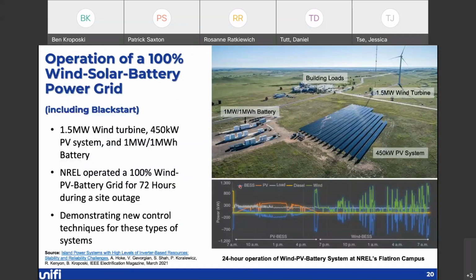I'll just point out that, again, these systems are not impossible to build. This is an example. We actually had our substation at one of our campus facilities go out on us, where we lost the utility for several weeks. But since we have lots of assets around, we quickly took a large wind turbine, PV system, and battery bank, configured it in such a way to actually run and operate our building loads, and we were actually able to show that we could run this for 72 hours without any grid, a 100% inverter-based microgrid, if you will. Although this wasn't reconnecting back into the grid itself, it did operate as an independent microgrid for 72 hours.